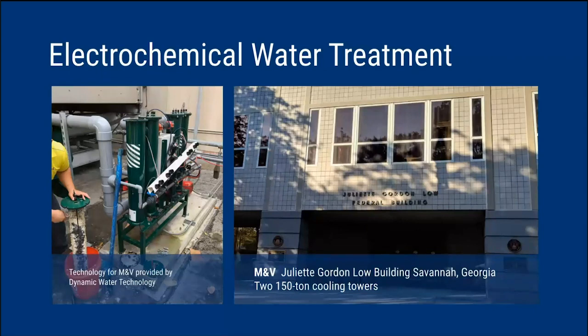So we installed this at the Juliette Gordon Low building in Savannah, Georgia. They have two 150-ton cooling towers at the site. As you can see on the left, this is the technology that we assessed, the dynamic water technology, which is an electrolysis technology. As you can see, it's a small skid. In this case, it's got 4 electrolysis canisters that sit right next to the cooling tower on the roof, and they actually take a slip stream of water. They don't treat the whole circulating water system. They just tap into the cooling water line as it discharges from the cooling tower and then discharge after the system back into the cooling tower. Next slide.